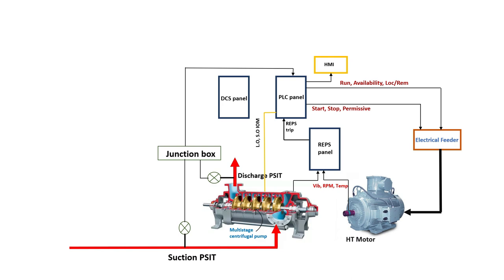These are all the multi-stage pump skid control signals. The rotary equipment protection system indications are communicated to the DCS through Modbus. Similarly, the PLC panel process parameter indications are sent to the DCS through Modbus cables. The DCS panel therefore receives both PLC panel control signals and rotary equipment protection system parameters via Modbus. The control room engineer can monitor the pump and motor from these indications — however, this is for indication purposes only, as control authority is given to the PLC and rotary equipment protection system.